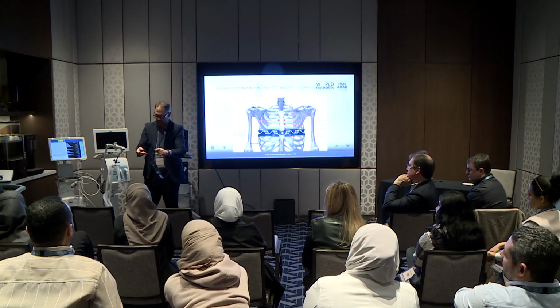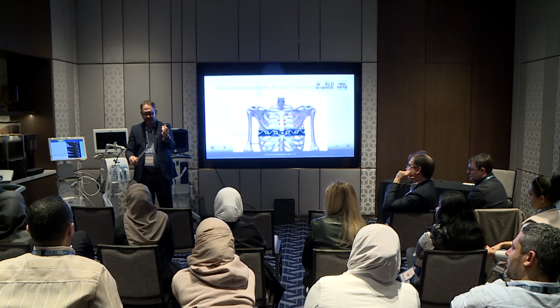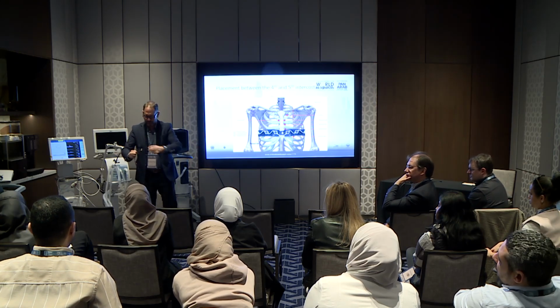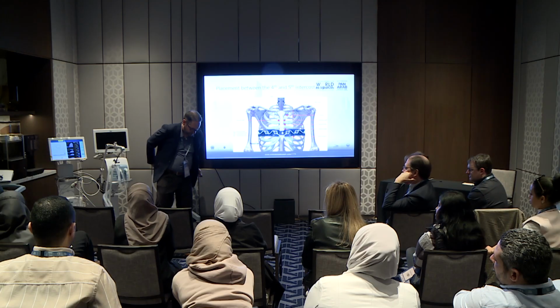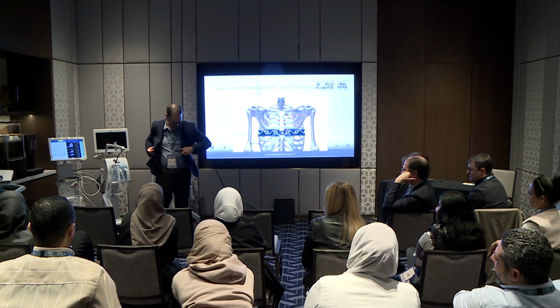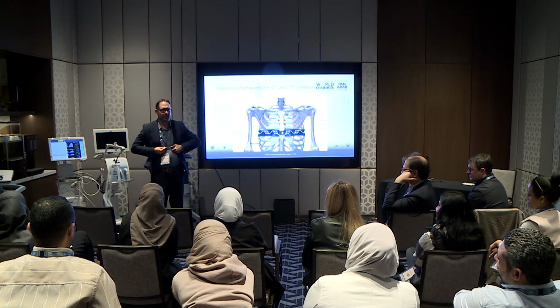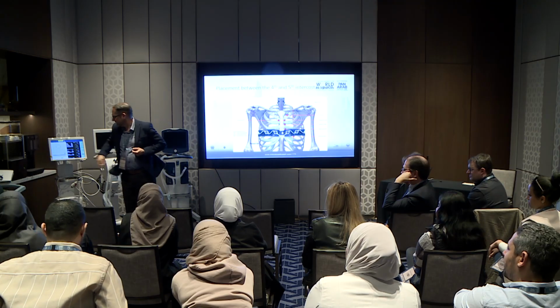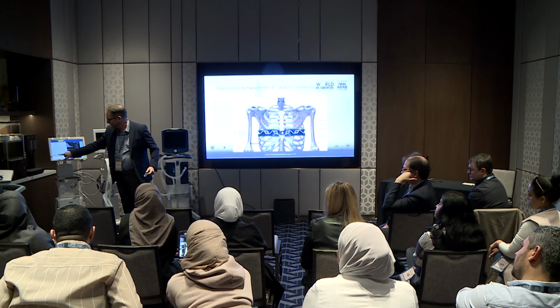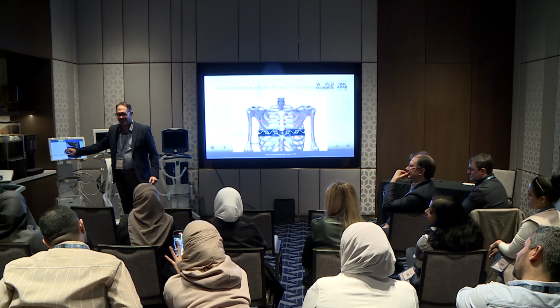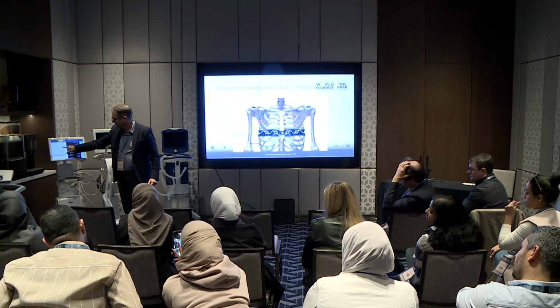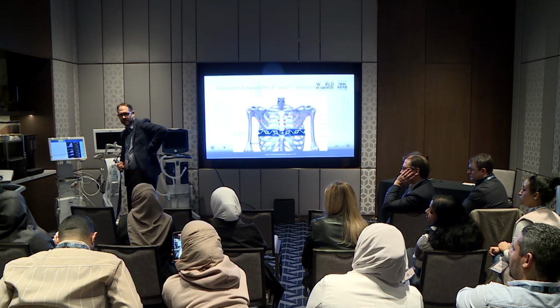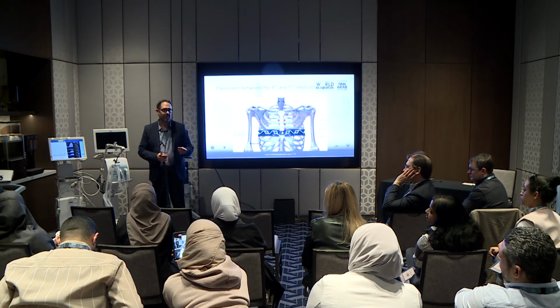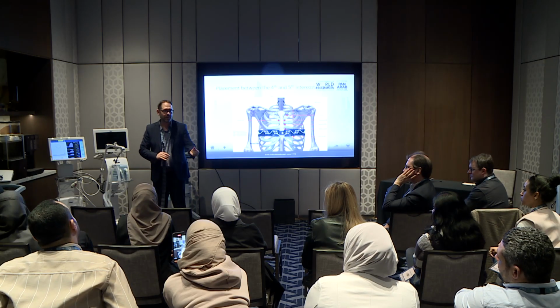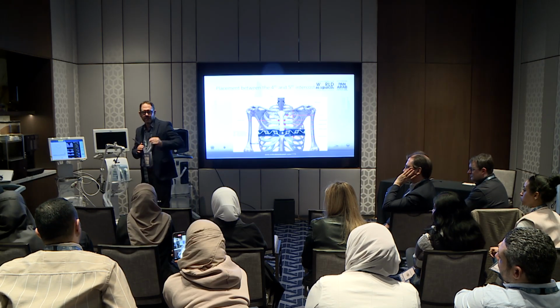one side is lead 1, and one side is, so this is 16, and this is 1. So when you place it around the chest like this, obviously I need more than a medium for myself, but when it goes around, you have 1 and 16, and it shows you right here, 1 through 16. So when there's a problem, it actually highlights it in red. So if it says 6, you go, oh, it's on the left side of the patient, number 6 is down here.